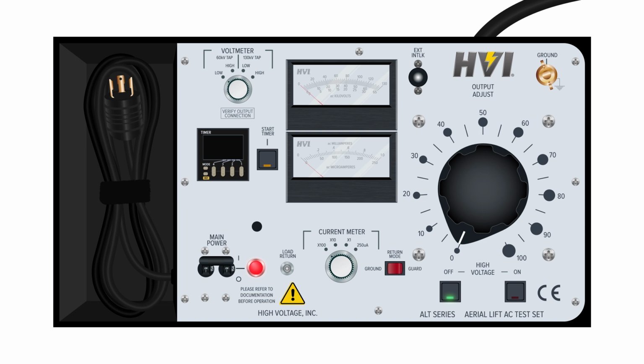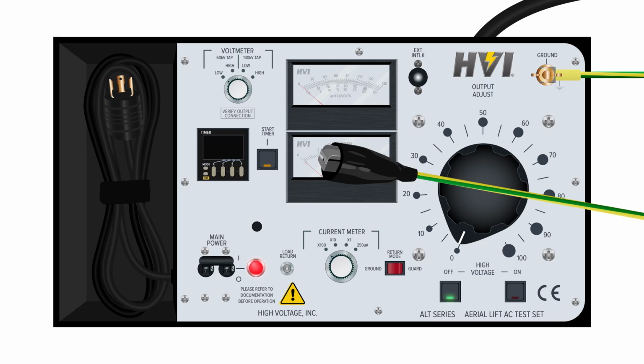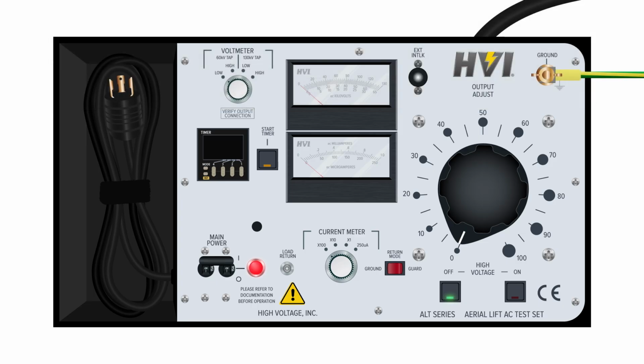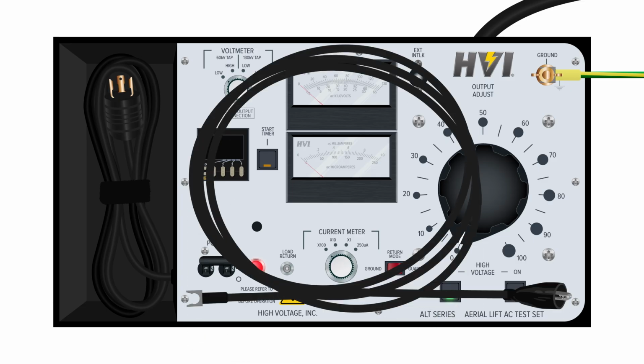First, connect the ground test lead to the upper right side of the panel on the ground post. The other end of the ground test lead has a black booted alligator clip. Ground the ALT series device to a solid earth ground with the alligator clamp. Repeat the process for the high-voltage section using the included secondary ground lead.